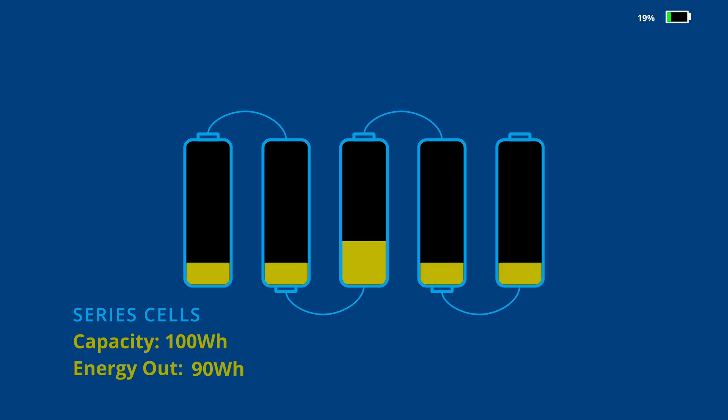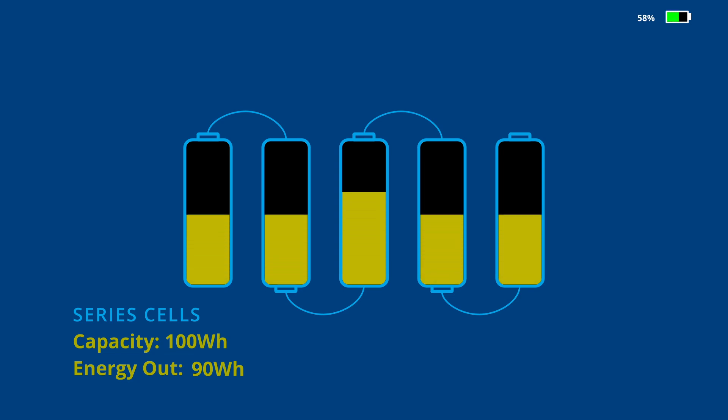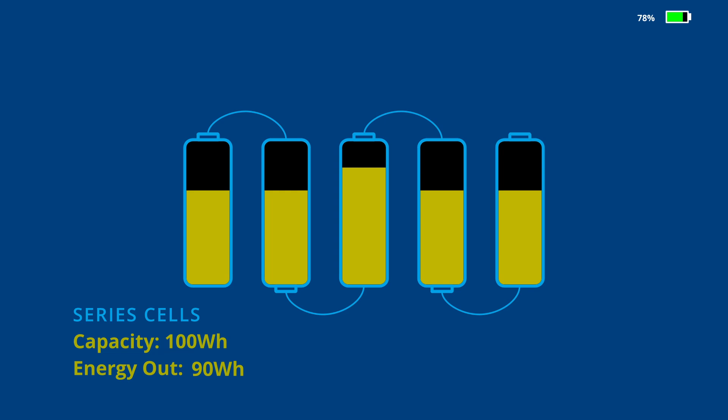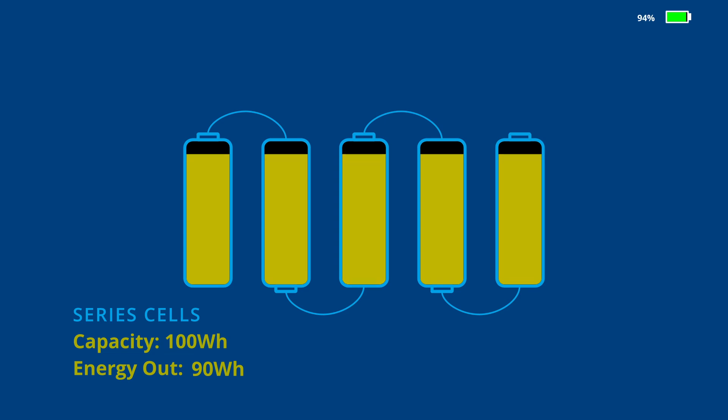This is why the battery management system, sometimes called the BMS, is so important. Once a sufficient state of charge is reached, the BMS can activate small bleed resistors across the highest cells, slowly draining just enough energy to bring them back into alignment, allowing the pack to be fully charged again.